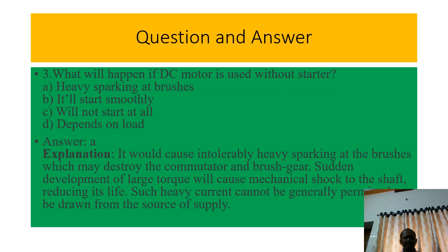The reason is that it would cause intolerably heavy sparking at the brushes, which may destroy the commutator and brush gear. Sudden development of a large torque will cause mechanical shock to the shaft, reducing its life. Such a heavy current cannot generally be permitted and drawn from the source of supply.